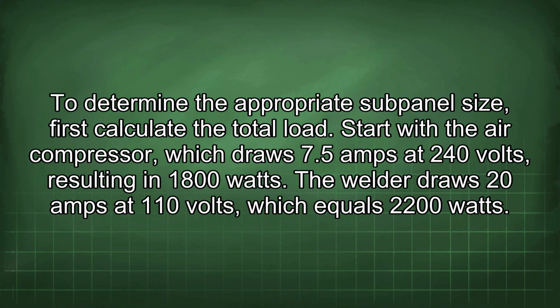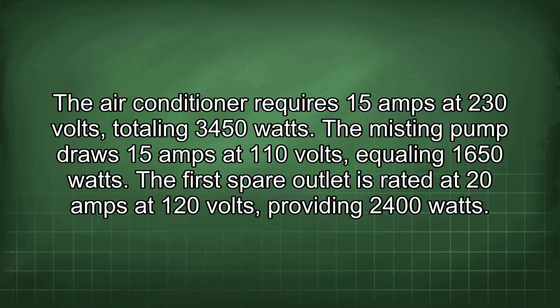To determine the appropriate subpanel size, first calculate the total load. Start with the air compressor, which draws 7.5 amps at 240 volts, resulting in 1800 watts. The welder draws 20 amps at 110 volts, which equals 2200 watts. The air conditioner requires 15 amps at 230 volts, totaling 3450 watts.